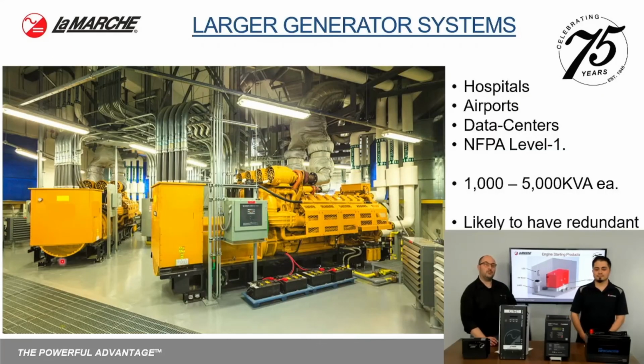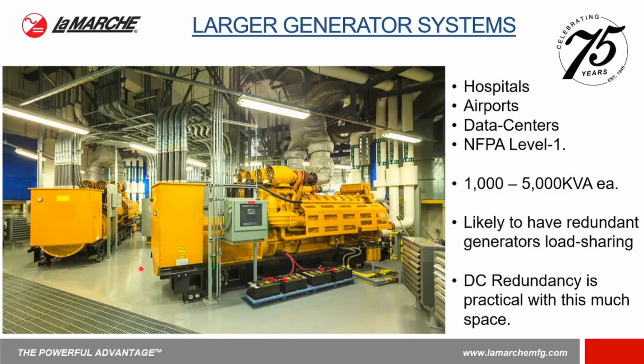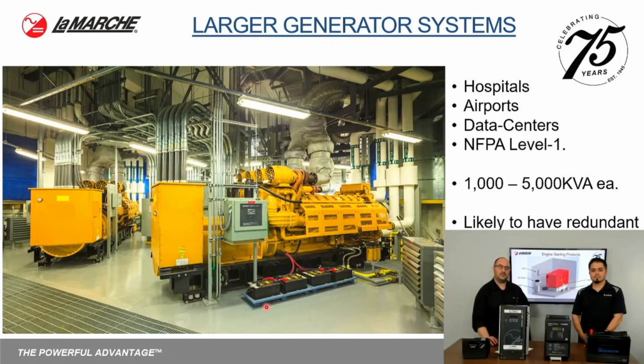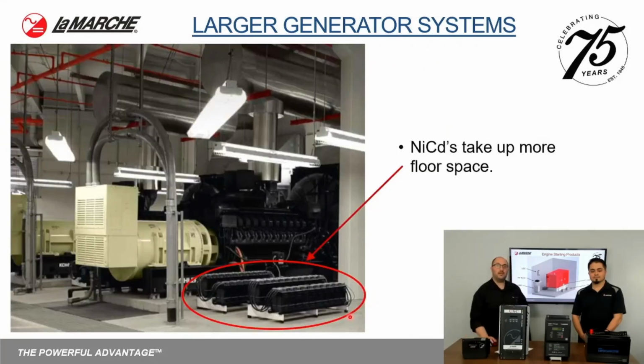Now when you get into a larger generator application, such as this might be hospitals, airports, data centers. These would be probably classified NFPA level 1. Your generators in this class might be between 1,000 to 5,000 kVA apiece, and they're likely to have redundant generators, such as in this image, that are doing redundant load sharing. So in a space like this, and here's our A12, and you can see the 8D batteries lined up on the side. Because there's so much floor space here, this is a good opportunity for redundancy.